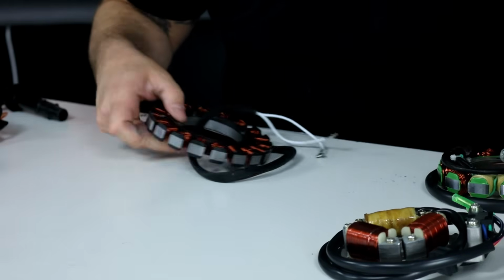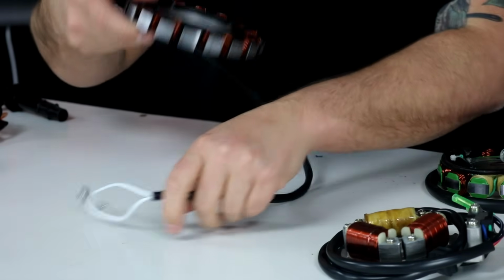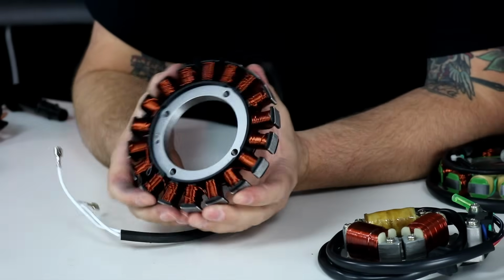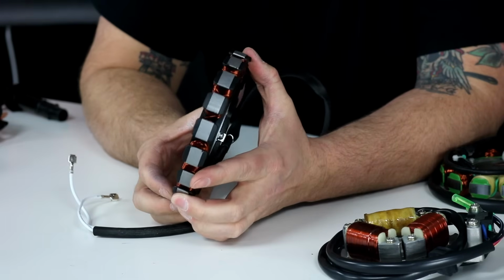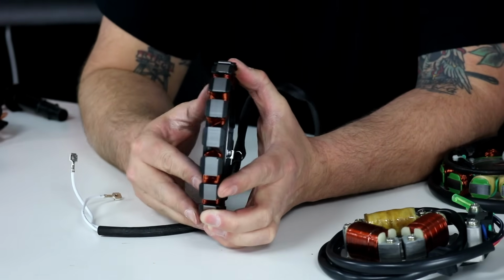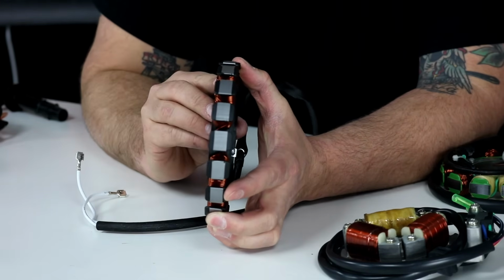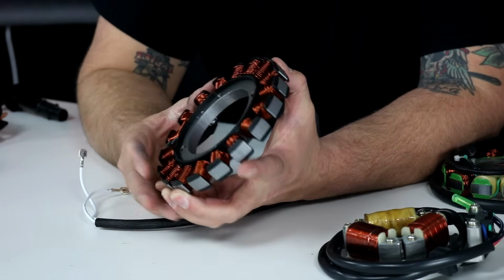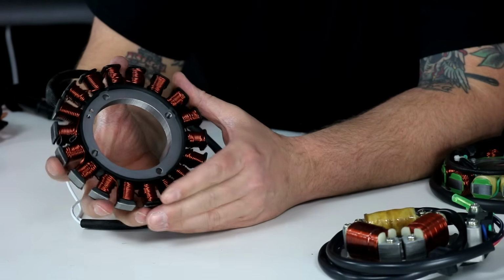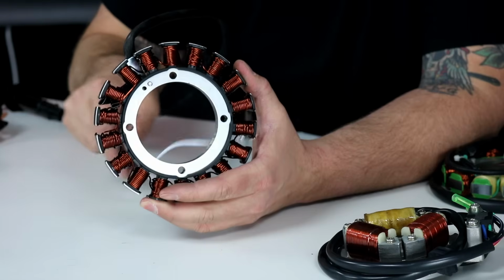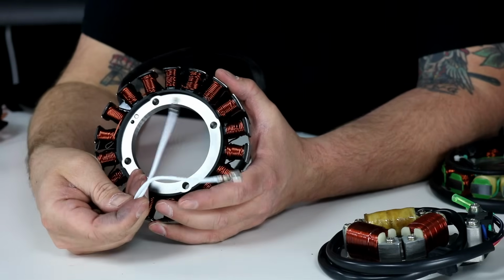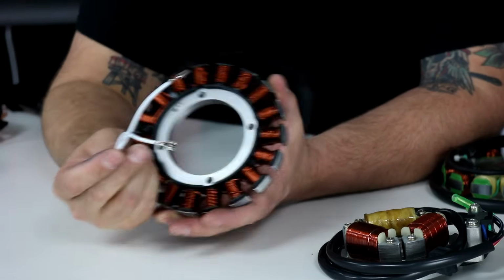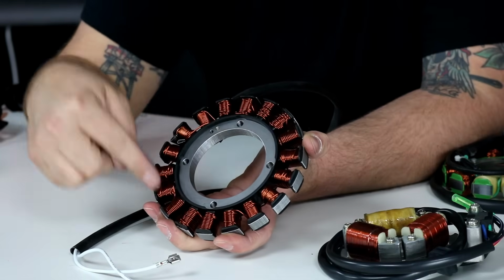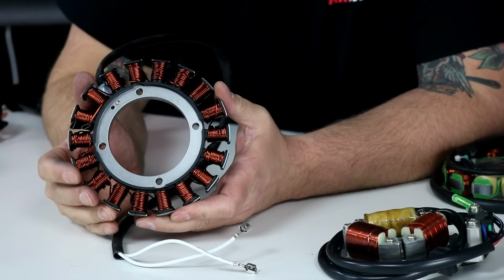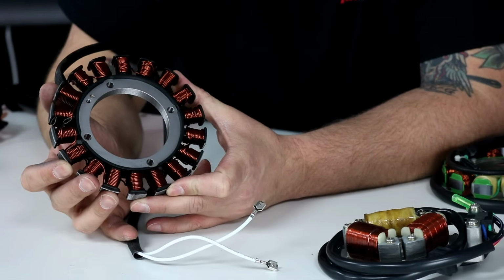Let me show you this one. It's basically the same thing, but a lot different shape, size, and dimensions - you can tell. It's still made up of separate laminations riveted together just like the other one, but it's obviously a lot larger and thinner. This is what's called a single phase stator, and you can tell it only has 2 wires coming out of it. That's because this is actually one coil wrapped all the way around - it doesn't have multiple coils that alternate like the other one I showed you.